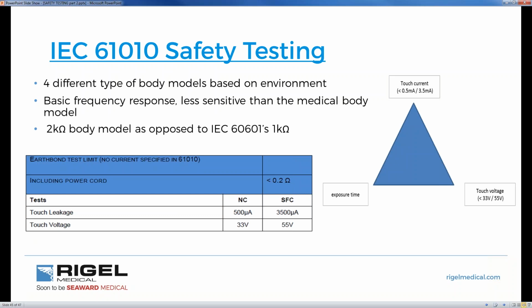The testing which we stipulate at Rigel, and which is part of a general safety test, there's no current within 61010. There's nothing specified to stipulate bond testing, but we give 0.2 because that's generally accepted across a lot of high pot testing and the experience that we have as manufacturers. And then we have normal condition and single fault condition, both touch leakage and touch voltage thresholds. The 61010 uses a different body model to what the medical body model uses in 60601. So the frequency response is less sensitive than that of a medical body model.